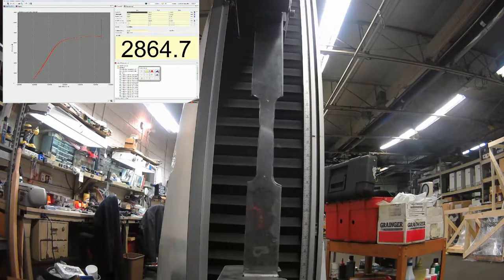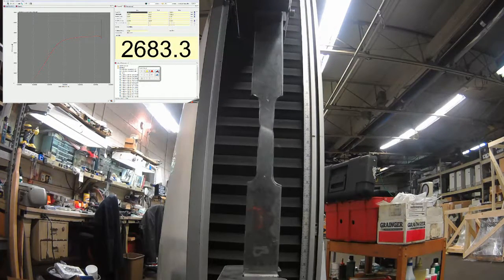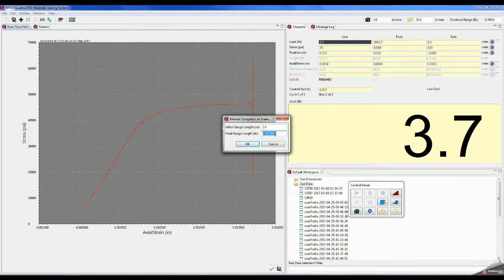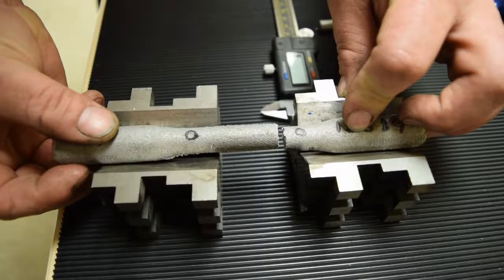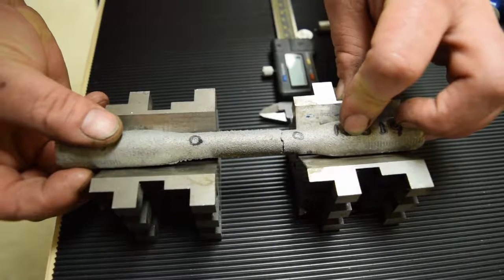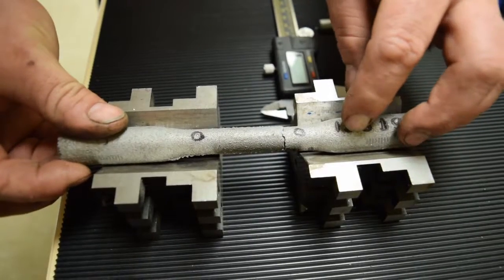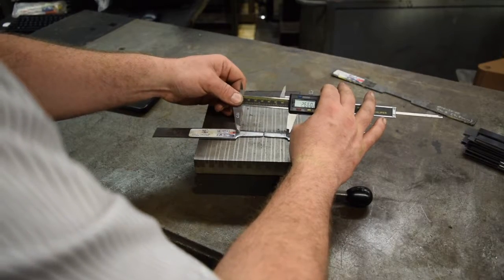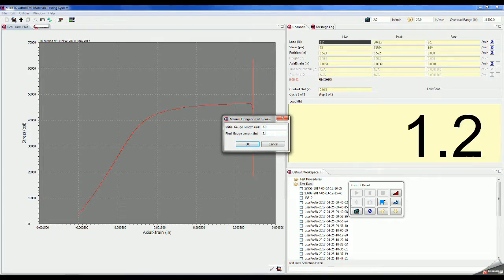Now that the sample has failed, you will be prompted by the program to insert a final gauge length. Remove the specimen at this time and reassemble it on a flat surface. Measure the distance between gauge punch marks and input it into the software, as seen here.